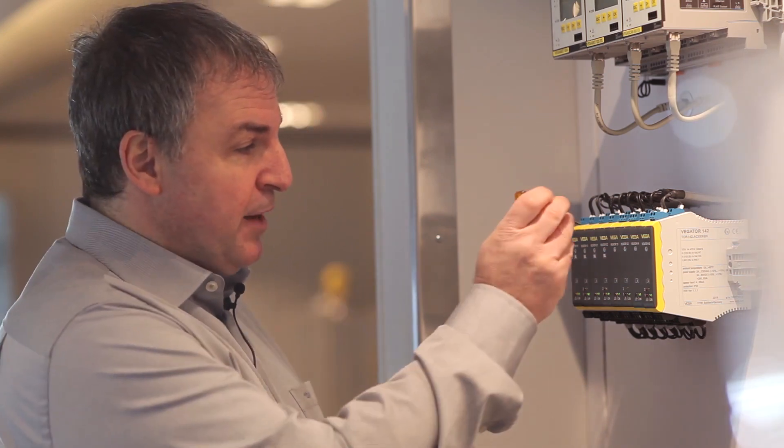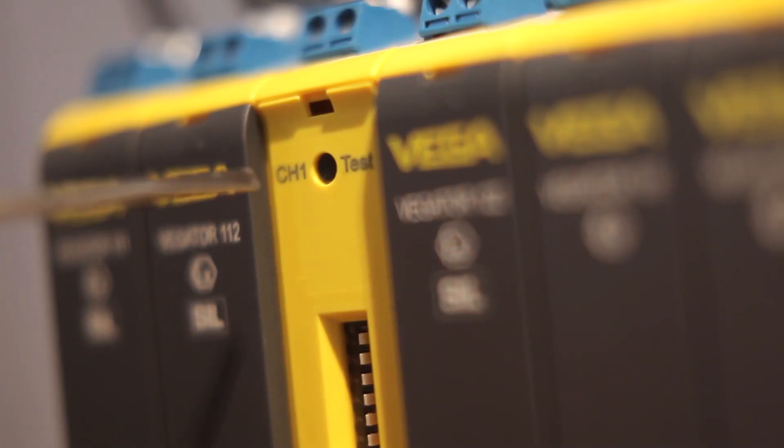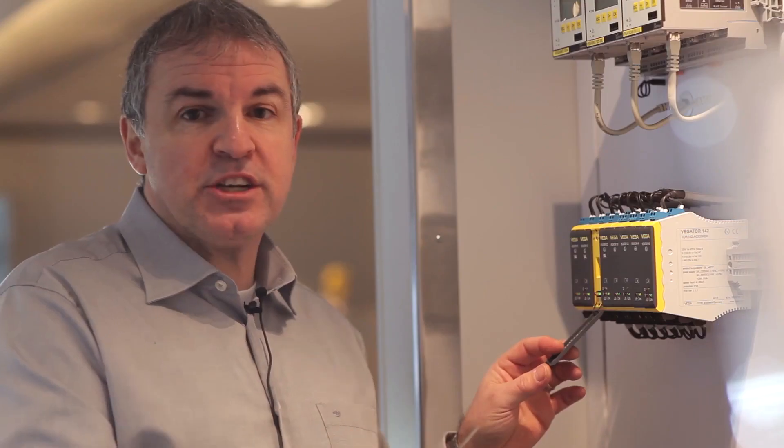Testing is much easier by using signal conditioning instruments Vegator. Behind the front cover you will find the test button. By pushing the test button one second, the automatic test will be generated and sensor and the connection will be tested.